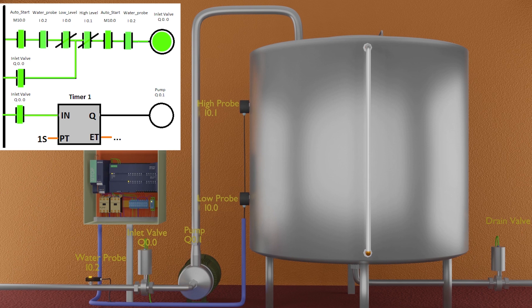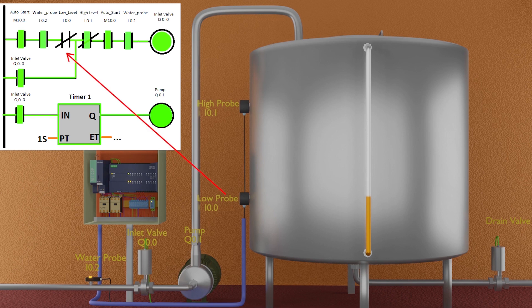After 1 second delay, pump output Q0.1 turns on. Now tank starts slowly filling with the water. As soon as water touches the low level probe I0.0, its normal close contact opens up, but the valve and the pump stays on because they are latched on.